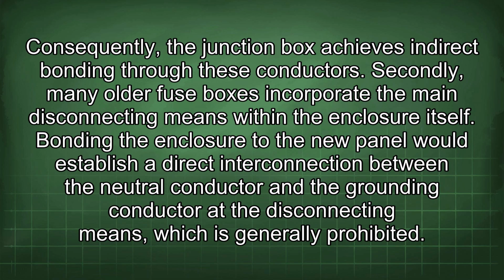Secondly, many older fuse boxes incorporate the main disconnecting means within the enclosure itself. Bonding the enclosure to the new panel would establish a direct interconnection between the neutral conductor and the grounding conductor at the disconnecting means, which is generally prohibited.